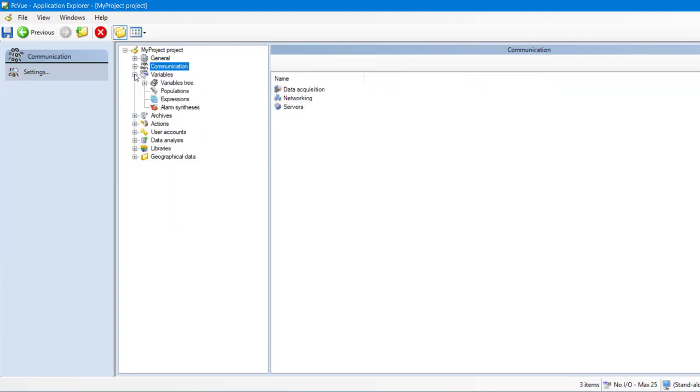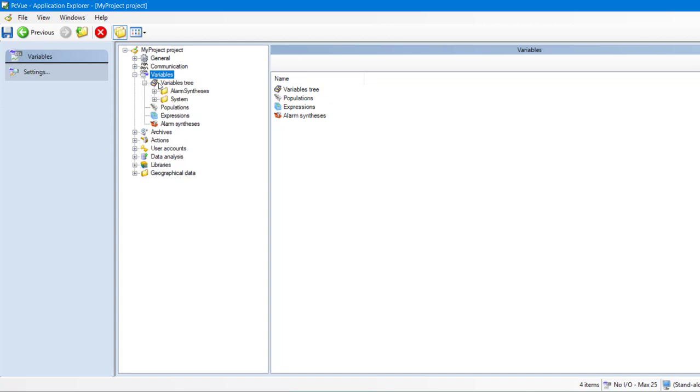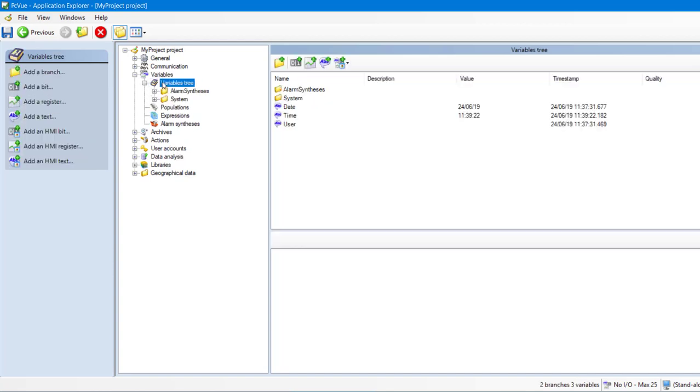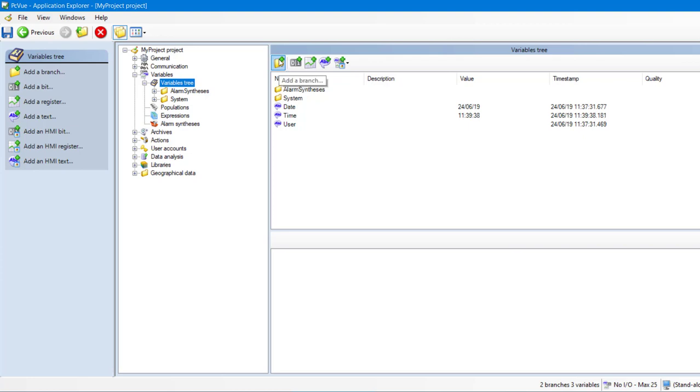The Variable section defines the way the data is organized. It is the core of PCVue containing a set of tags called Variables. The variable tree organizes data in a hierarchical manner using a branch structure. For example, to create a real-time database for a simple building management system, you just enter each element of your physical process as a branch. Let's imagine a building and create a new branch.